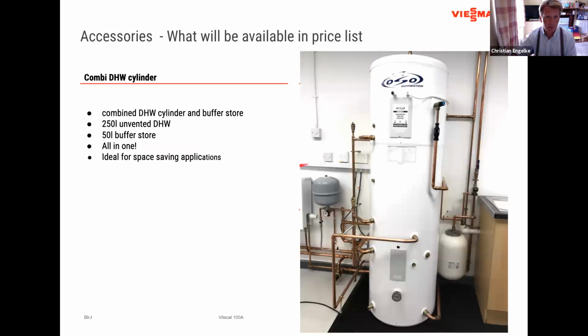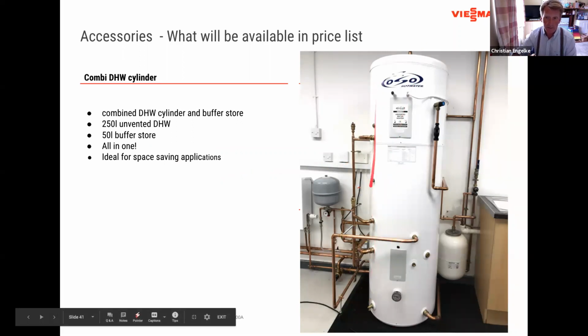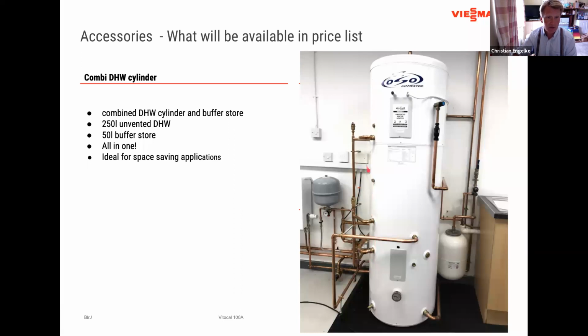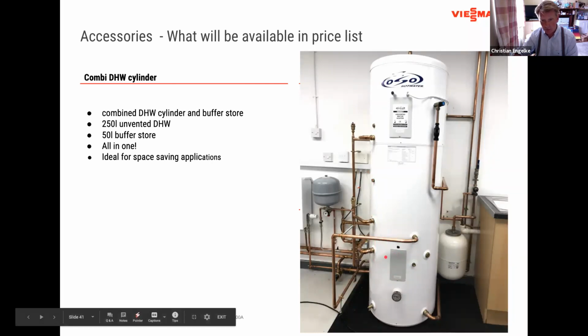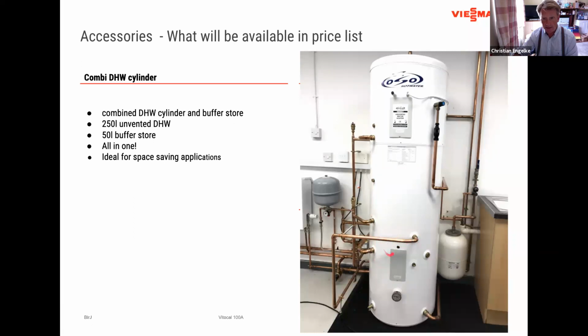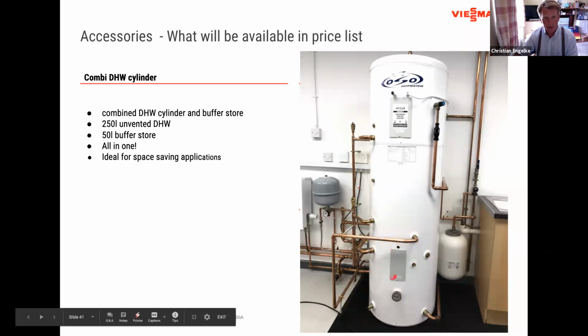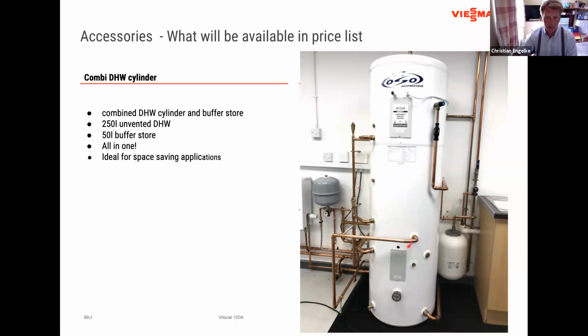And finally, we have an accessory which will be very important for you. This is a combined hot water cylinder and buffer store, all in one unit in this slick design. A 250 liter hot water cylinder is available, and underneath, separate from the hot water, so it's obviously not linked to each other, but a separate design, is a heating buffer store of 50 liters. All in one, so you don't need any extra space for the buffer store wherever it's required. And then the storages can also be fitted with additional immersion heaters where and if required. So that model will be available together with the heat pump.